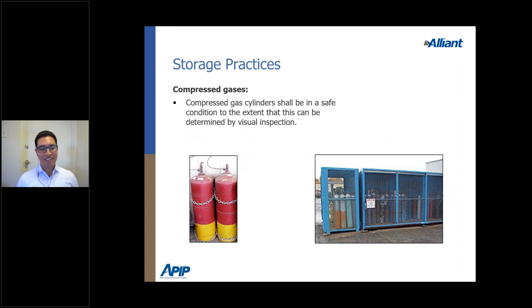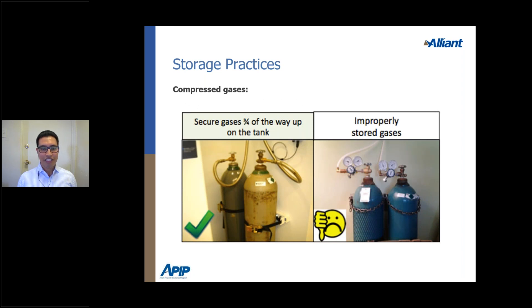With compressed gases, always refer to the SDS for proper storage guidance. Tanks must be secured — at two-thirds height from the bottom — with a strap or chain secured to the wall. The picture on the left shows proper storage at two-thirds height; the picture on the right shows strapping near the top, which is incorrect. This prevents tanks from toppling over during a crash, earthquake, or similar event and emitting dangerous gas.